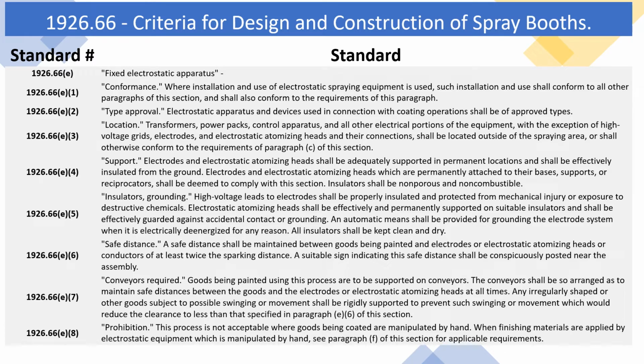1926.66 E4. Support. Electrodes and electrostatic atomizing heads shall be adequately supported in permanent locations and shall be effectively insulated from the ground. Electrodes and electrostatic atomizing heads, which are permanently attached to their bases, supports, or reciprocators, shall be deemed to comply with this section. Insulators shall be non-porous and non-combustible.